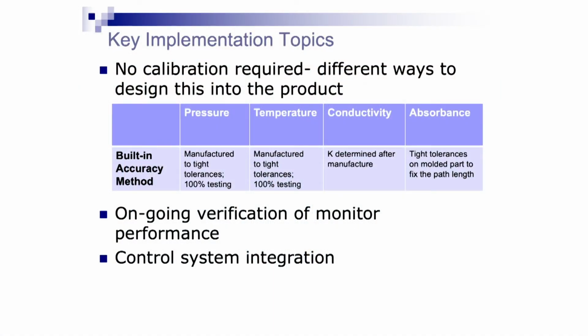So one important thing in any single-use technology, whether it's batch or continuous, is again the need to not calibrate. So these are key implementation topics. You don't want to have any calibration required. So for each one of our technologies, we have a means to eliminate the need for calibration. The pressure and temperature are manufactured to tight tolerances, so essentially each one of them is the same. For conductivity, we predetermine the K factor, so the user doesn't have to account for uncontrollable differences in the conductivity cell geometry. And for absorbance, we manufacture the path length to tight tolerances.